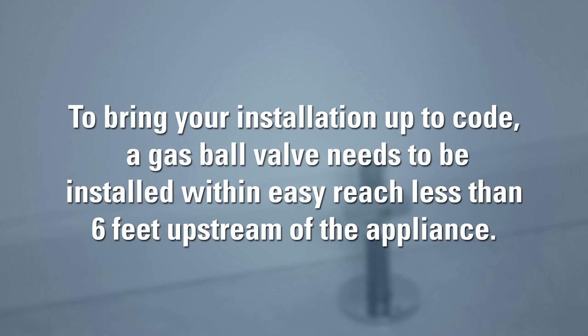To bring your installation up to code, a gas ball valve needs to be installed within easy reach, less than six feet upstream of the appliance.